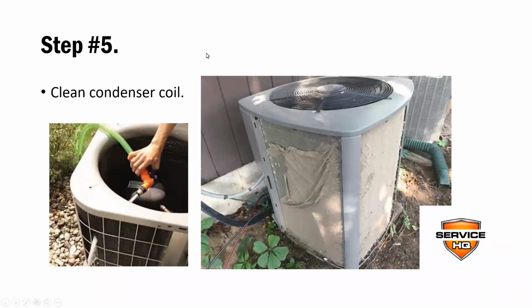So next, we clean the condenser coil. Once we know that the power is off, we like to wash the condenser coil from the inside out, because air is being sucked into the coil this way. So when we wash it, we push it back out the way it came. And if the unit has panels, like this unit right here has no panels, but this one does, and these panels have been removed, you can see the coil here, and you see this blanket of junk, which is cottonwood, those little puffy balls of cottonwood floating everywhere. Usually that's what causes that. Sometimes we see a bunch of grass, like people will drive their mowers right by their machine while it's running, and it just sucks that grass right in there.